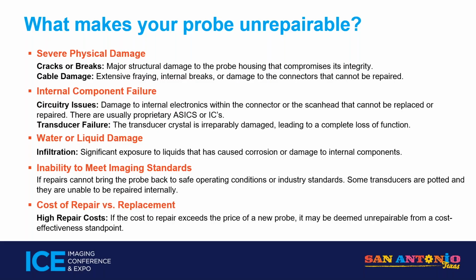So again, routinely check your probes if you're in front of an ultrasound. Should be at least every 6 months if you do PMs that way, right? Even once a year is better than just doing GE, no PMs required, right? Internal component failure, it happens. What's a common failure that everybody sees on probes when an internal component fails? That's one that we get calls on all the time.